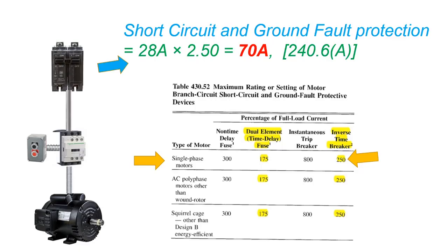For short circuit and ground fault circuit protection: 28 amperes times 250 percent equals 70 amperes, as per Table 430.52. The 250 percent is the allowable percentage of full load current for an inverse time breaker. The standard breaker size is selected from Table 240.6(A).